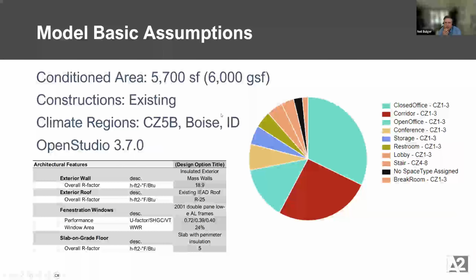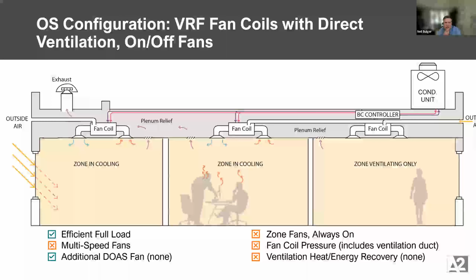All right, but we're going to walk through, if we applied different systems to this building, what are the results we could get out of it? So this first system we're going to look at is, and I realize we put, well, walk through it anyway, so it's just ducting outside air to the fan coil. So in this configuration, I realized I put this building in Boise, it probably wouldn't actually work in reality. You would need a little heater on the inlet of that air. The model still will run and just squeeze more heating out of this fan coil for purposes of demonstration. But this is, like I shared before, been done in certain buildings where they're really cutting costs and trying to find ways to make it all fit.